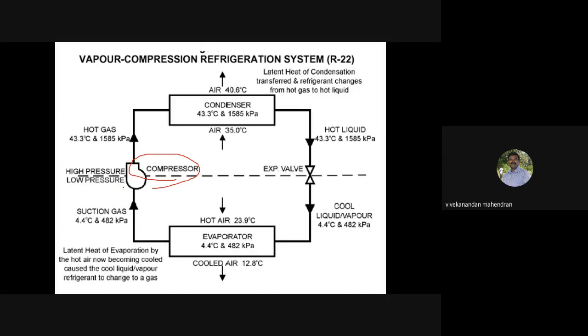Upon increasing the pressure, here is what it gets: 482 kilopascals, and 4.4 degrees is the inlet gas pressure and temperature. Upon getting higher pressure and temperature, it raises its pressure to 1585 kilopascals at a temperature of 43 degrees. As my pressure rises, temperature also rises. So this is gas, whereas gas won't obey the incompressible law of fluids.